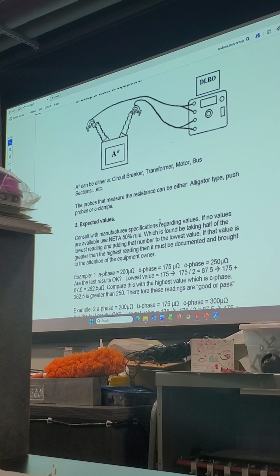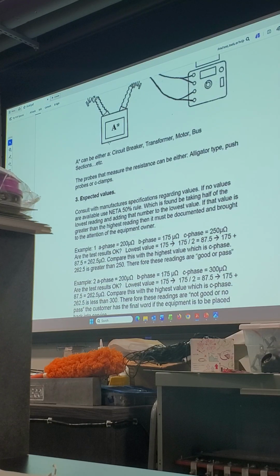Probes to measure the resistance can be either alligator type push probes or C-clamps. We don't necessarily use C-clamps for the equipment we've seen here, but this is going to be perhaps a high voltage connection, maybe up high in the air or subject to the elements, then you'd want a more positive connection like C-clamps. But in our controlled environment, mostly we're going to be working with alligator clips and push probes.